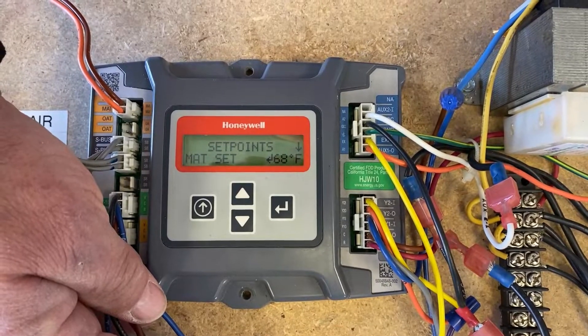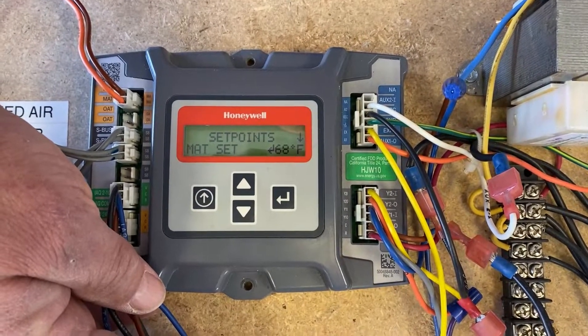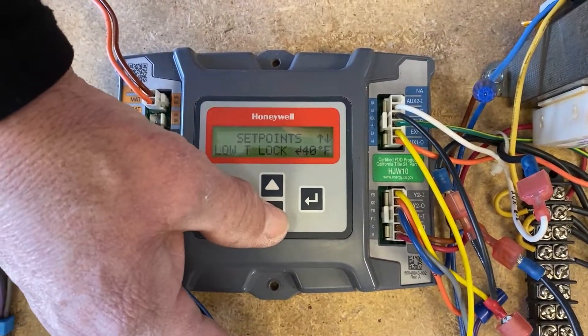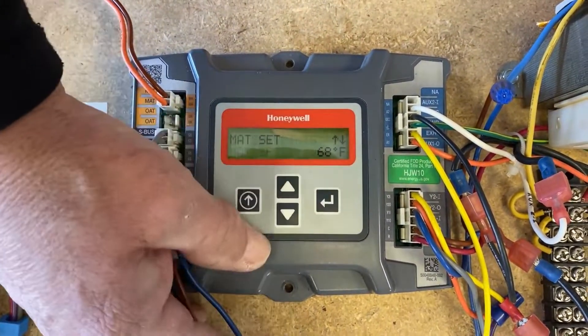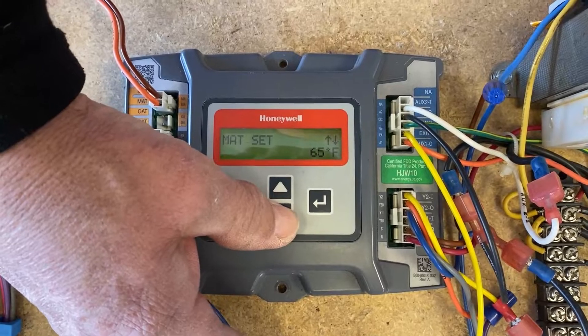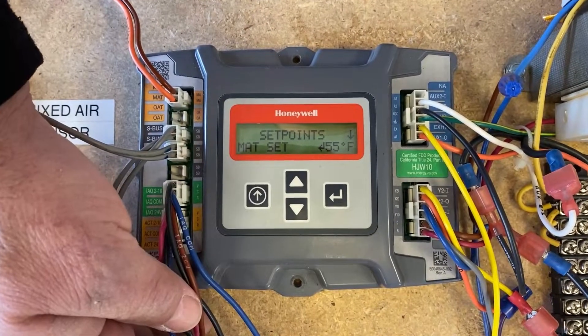Mixed air temperature set point — that's what you want for your mixed air temperature, and it's usually going to be around 55 degrees.